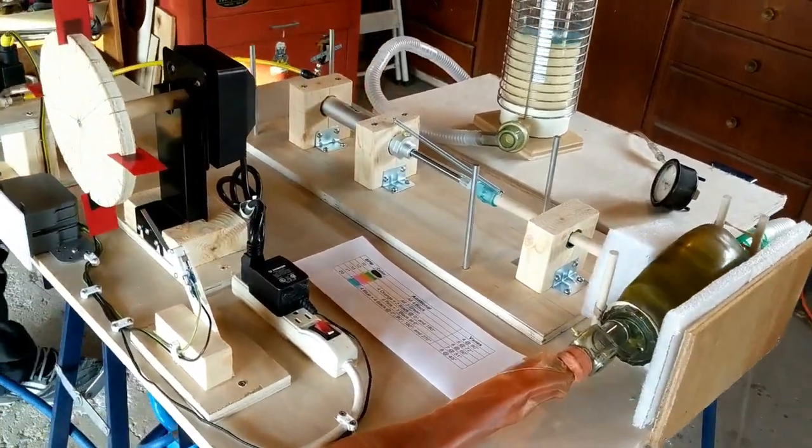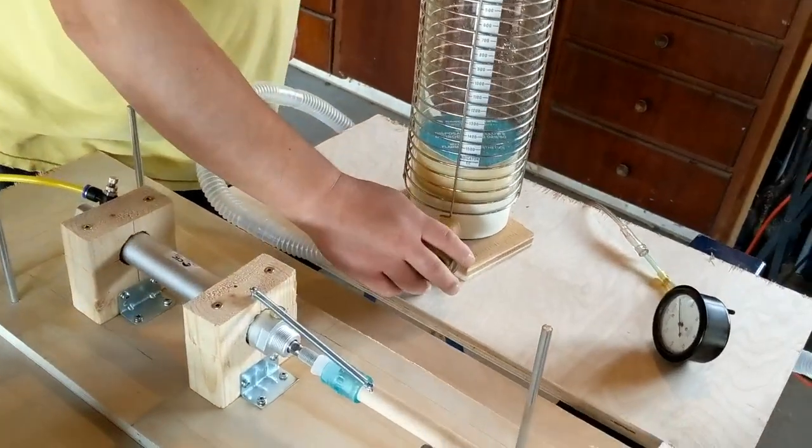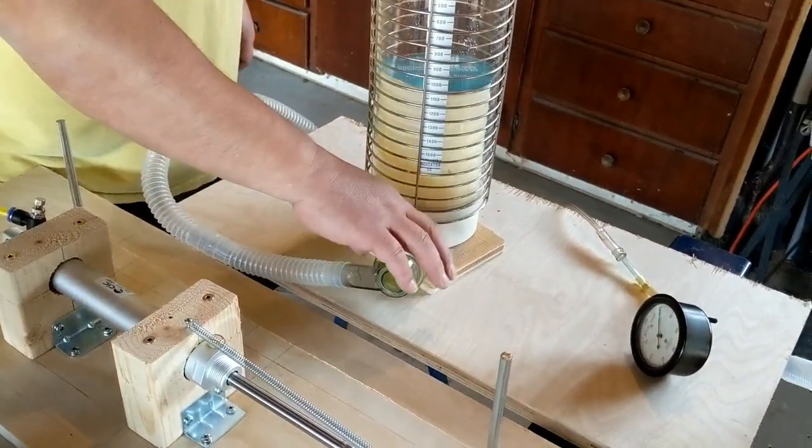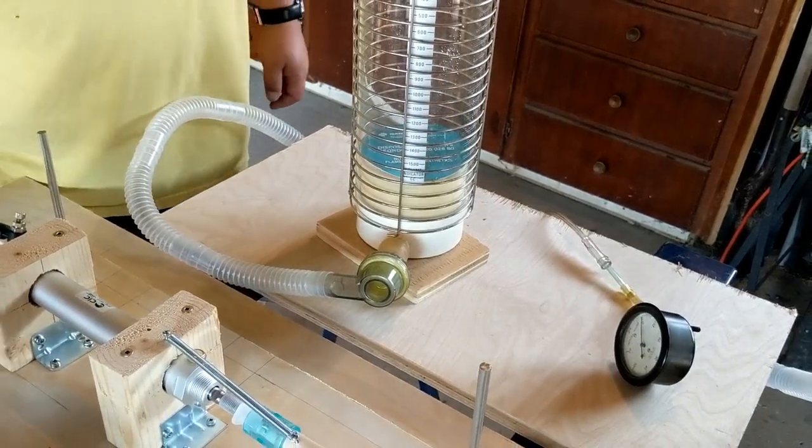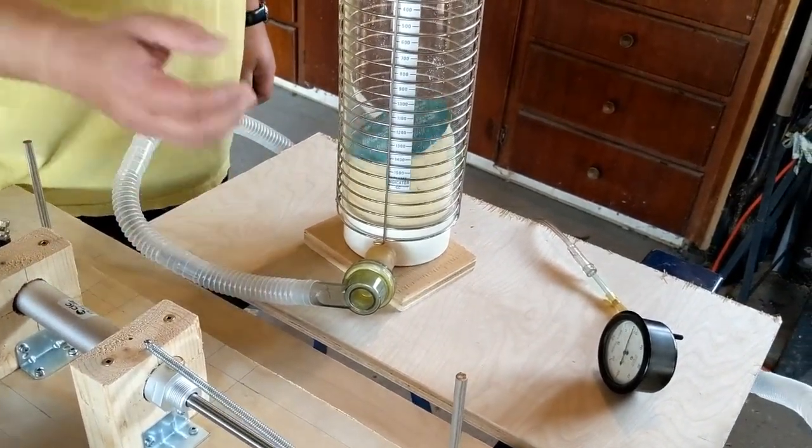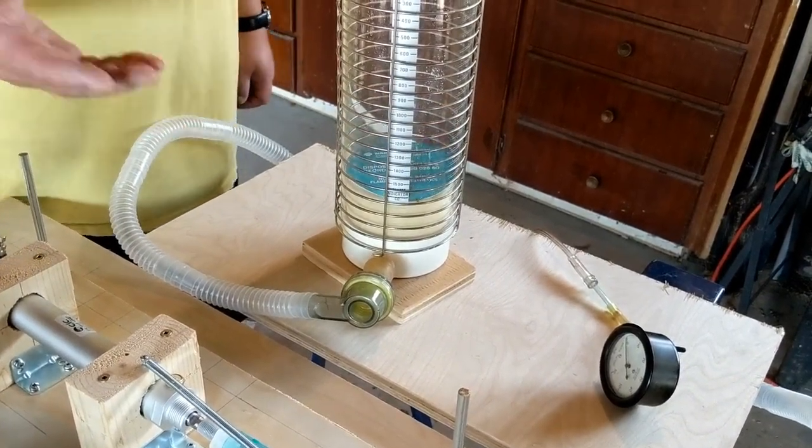Now for PEEP I don't have one, but Laerdal does manufacture a PEEP valve attachment that goes over the exhalation valve over here and typically would go to a PEEP valve. If you're running out of PEEP valves you can use this tubing, run it into a bucket of water 10 centimeters deep, 15, 5, whatever you want.